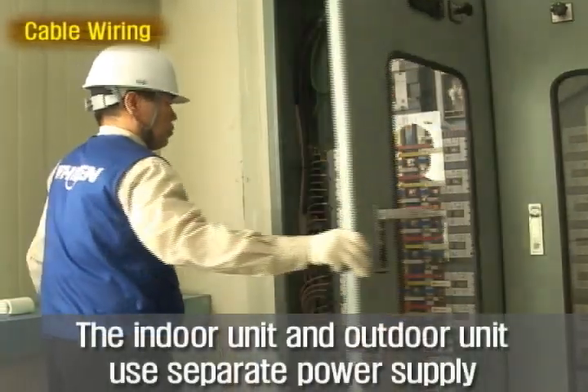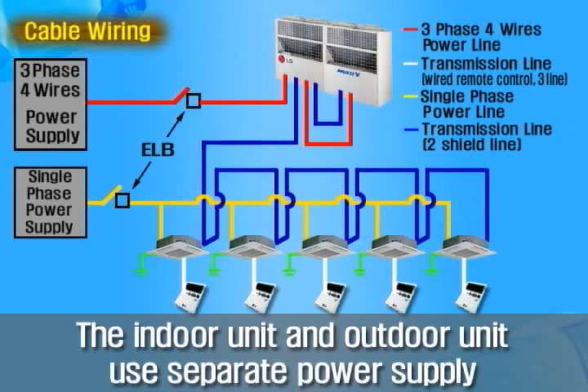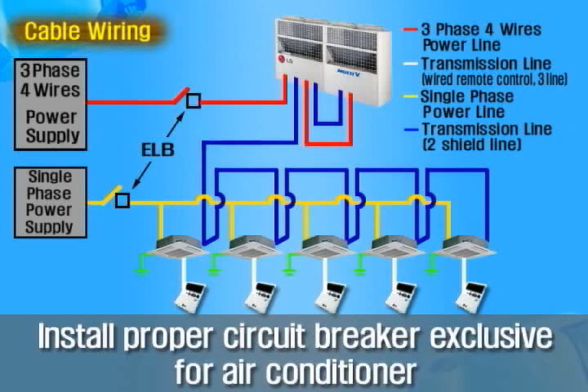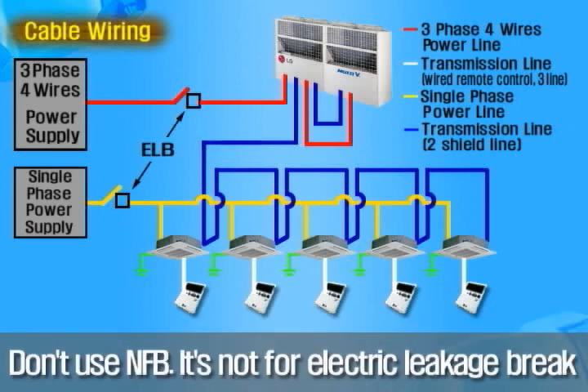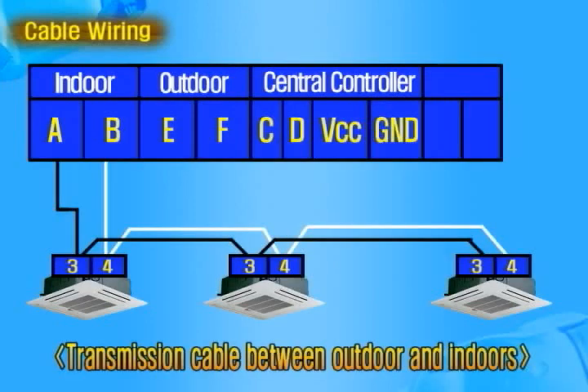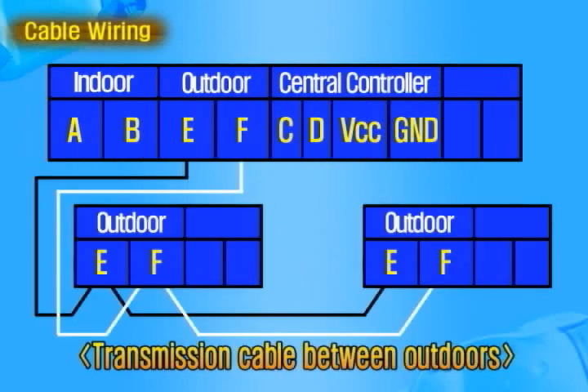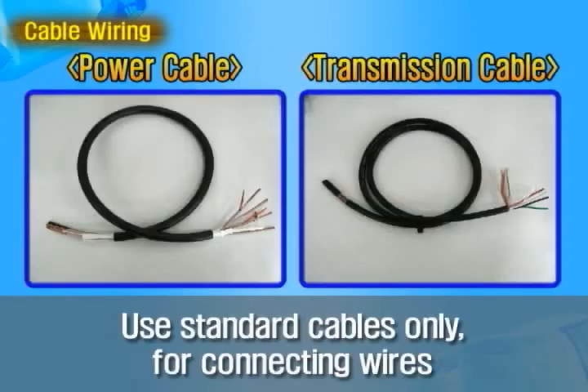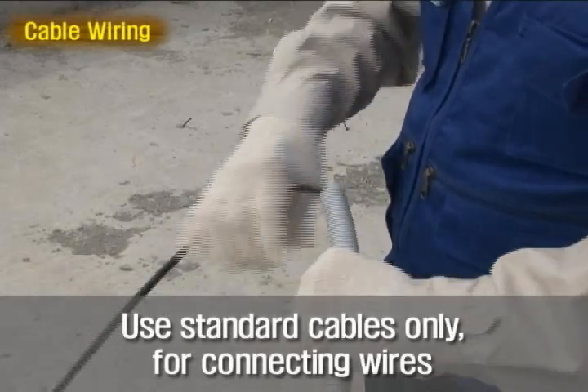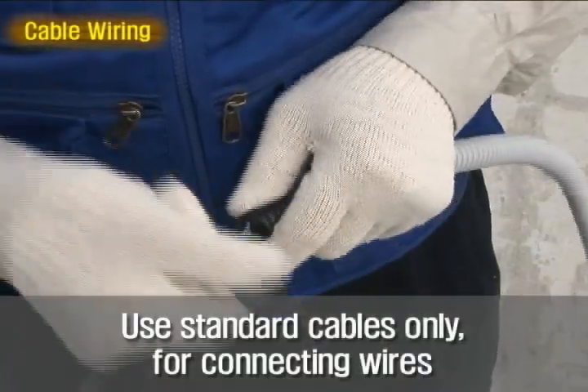The indoor and outdoor unit needs separate power supply. In starting wiring work, check if the circuit breaker exclusive for air conditioner is installed properly or not first. Transmission cables between outdoor and indoors and between outdoors should be connected like this figure. All the power and transmission cables should meet the standards. Insert them into the flame-retardant tube and close the openings for installation.